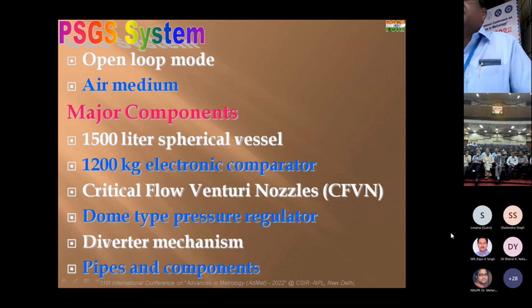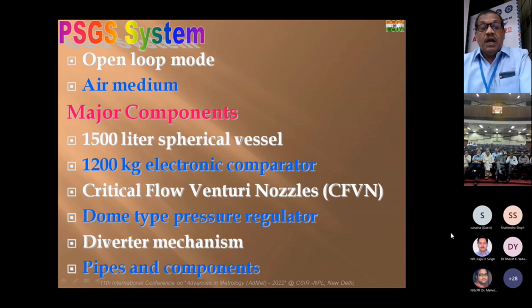Why we have selected the spherical shape is to reduce the quantity of metal, because that gives the maximum volume. So we want to reduce the overall weight of the container, and therefore we have made it in a spherical shape. It is placed on a 1200 kg electronic comparator, so directly we get the mass. And we use critical flow venturi nozzles, otherwise the sonic nozzles, a dome type pressure regulator to regulate the pressure and adjust the pressure at the test section, a diverter mechanism, and the pipes and other components.